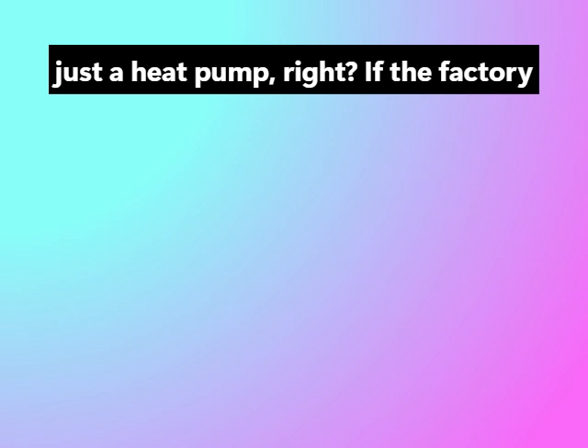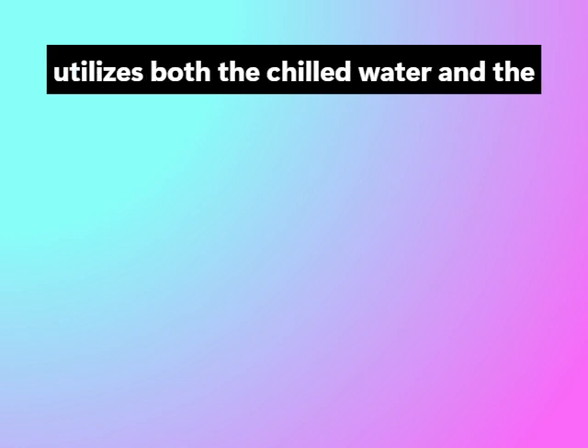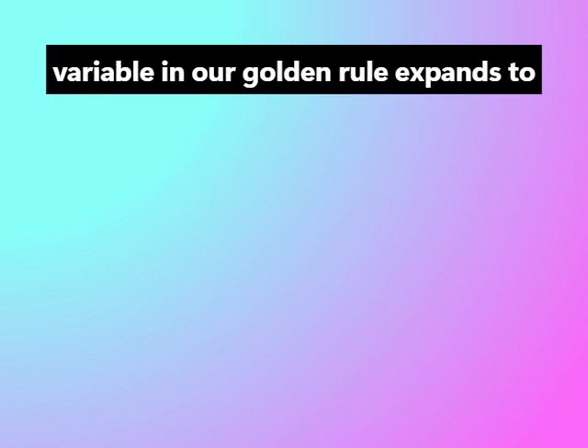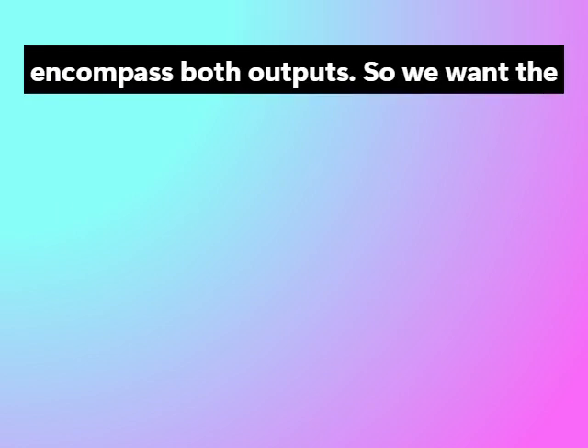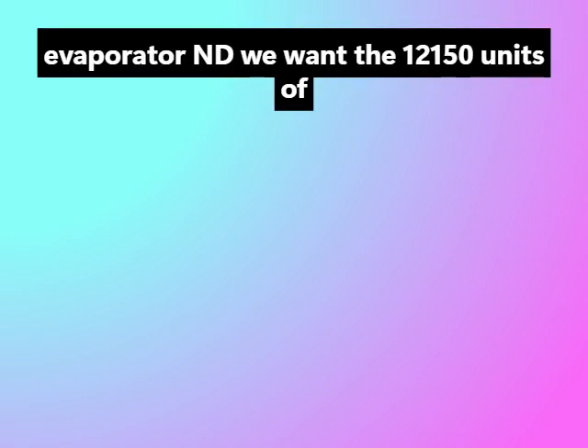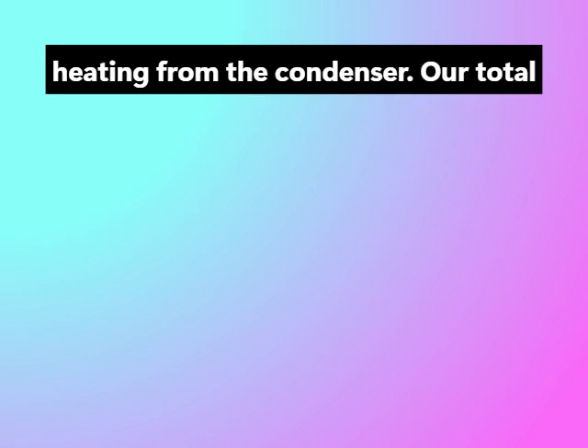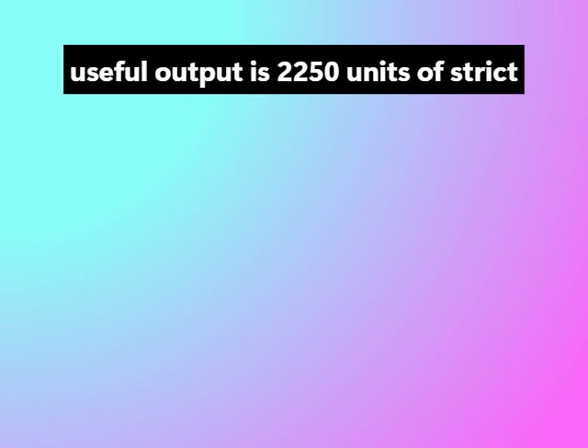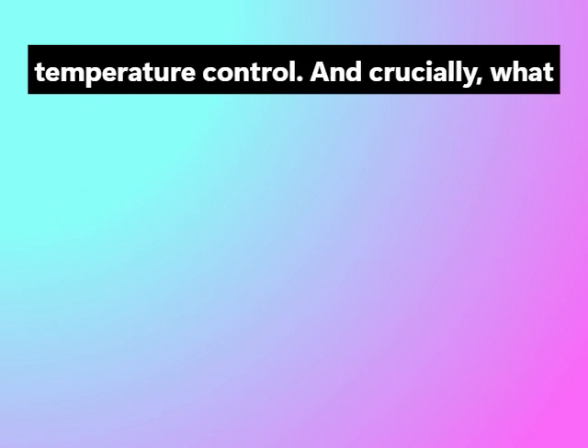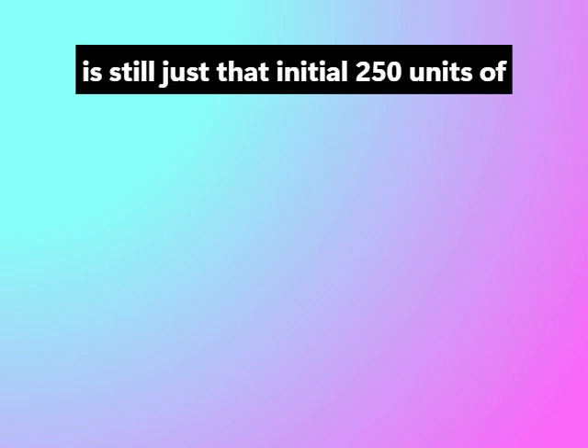If the factory utilizes both the chilled water and the hot water streams, then the what we want variable in our golden rule expands to encompass both outputs. So true. We want the 1,000 units of cooling from the evaporator, and we want the 1,250 units of heating from the condenser. Our total useful output is 2,250 units of strict temperature control. And crucially, what we pay for hasn't changed at all. Nope.